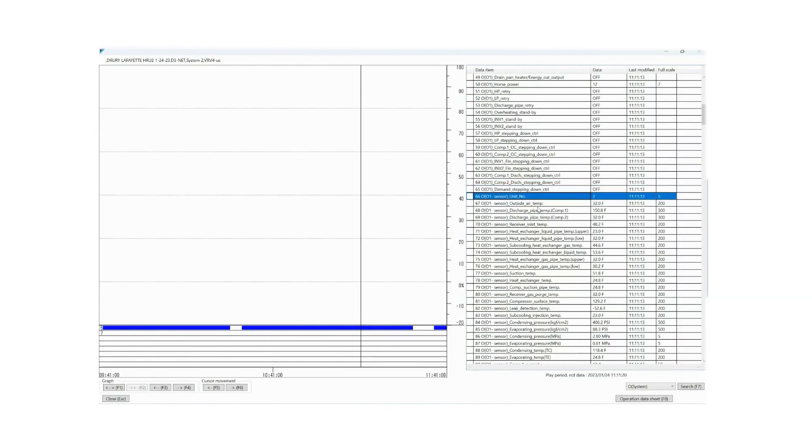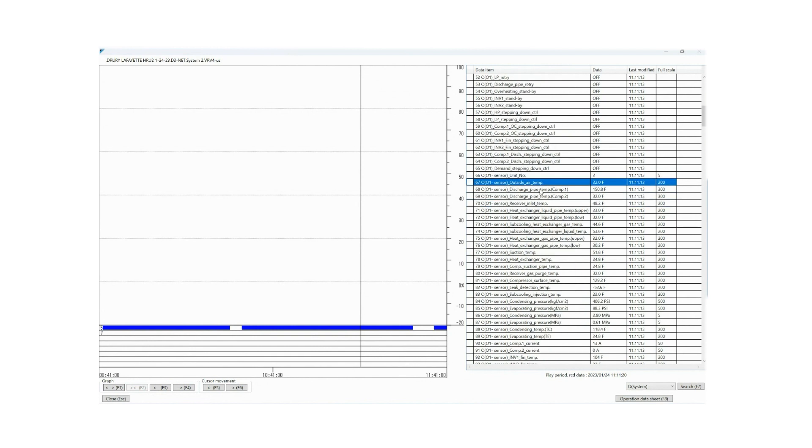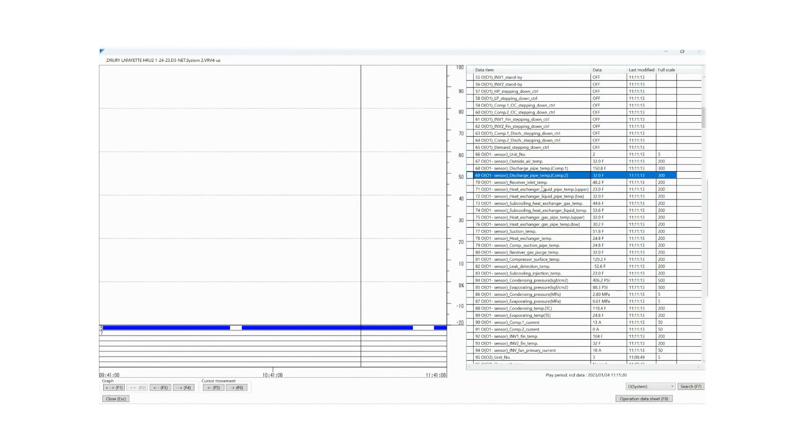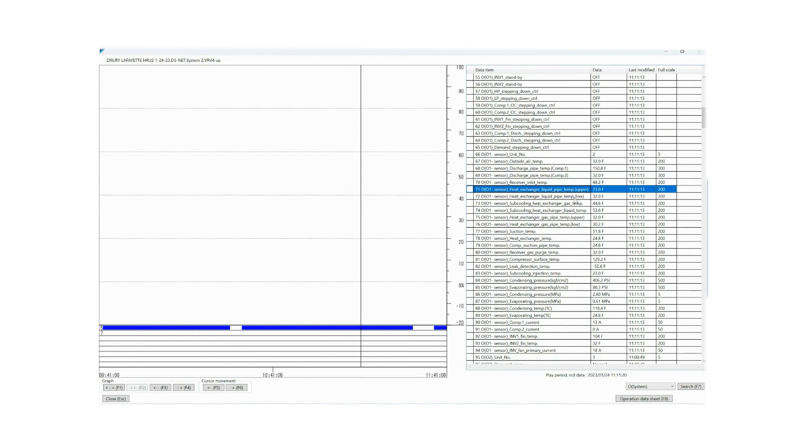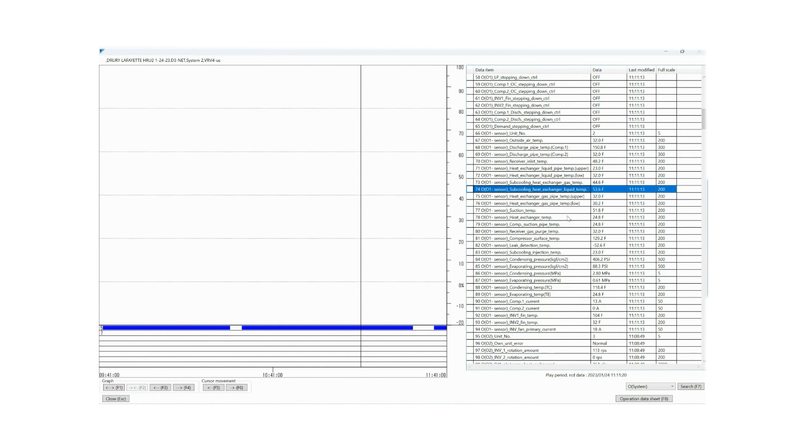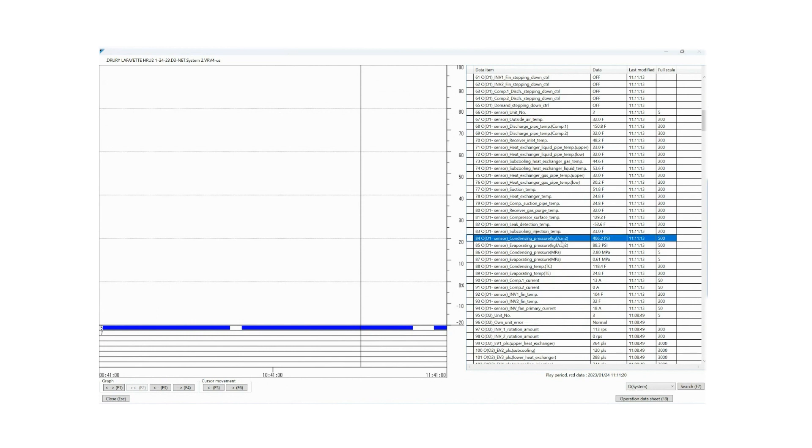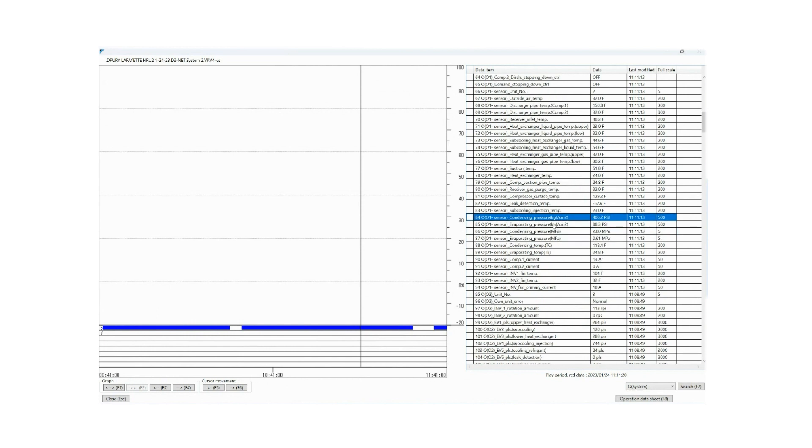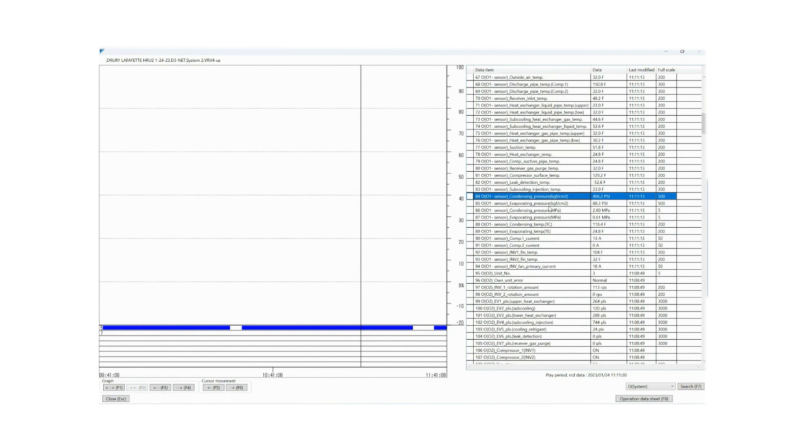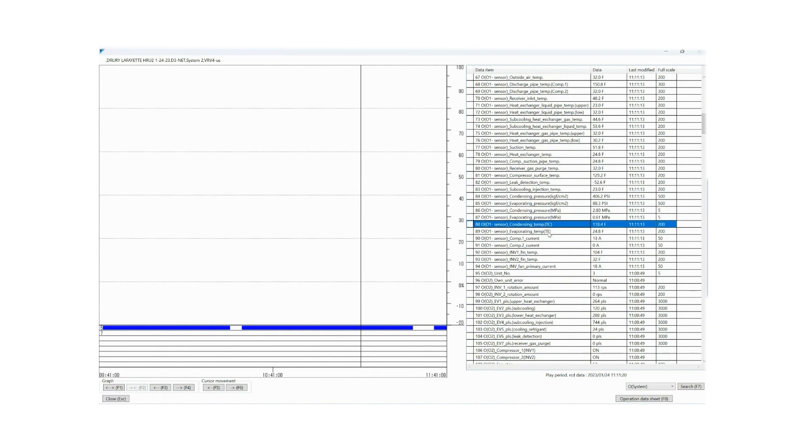Then you'll notice here, OU1, now we're getting into the sensors. We've got outside air temp, discharge pipe temp. Discharge pipe temp 2, compressor 2. I know that's 32 degrees, which is a null value, which means that this sensor is not being used in this module, which means that it's a single compressor module. Receiver inlet temp. Here's all your upper and lower heat exchangers and your liquids and your gas temps, sub-cooling valve temps. These are all of your thermistors. They get banked in one section inside the actual service checker. Leak detection temp not being used, negative 52.6. It's not something you should worry about. Sub-cooling injection temp. Then we get into our pressures.